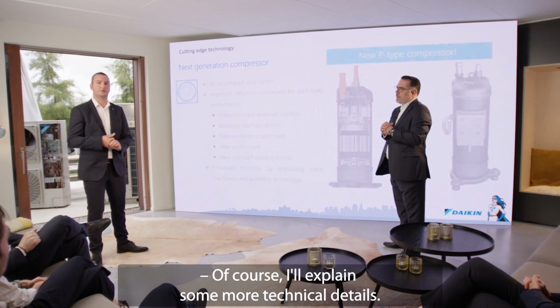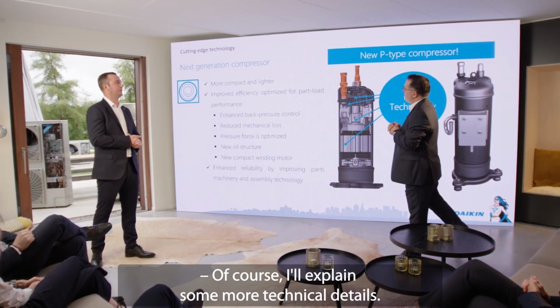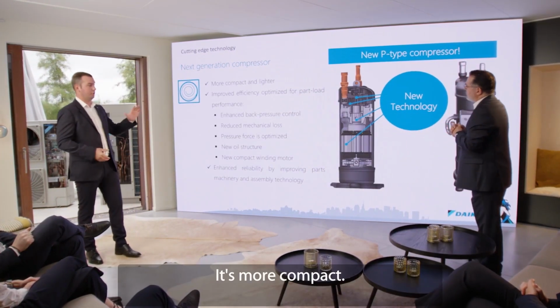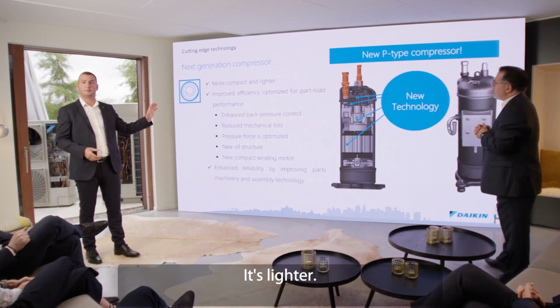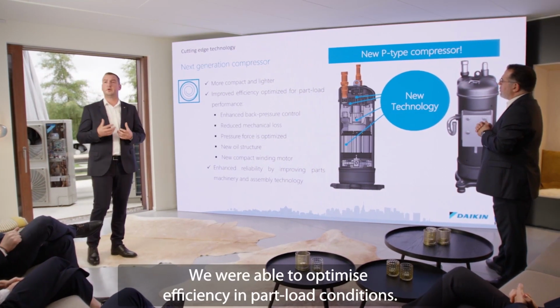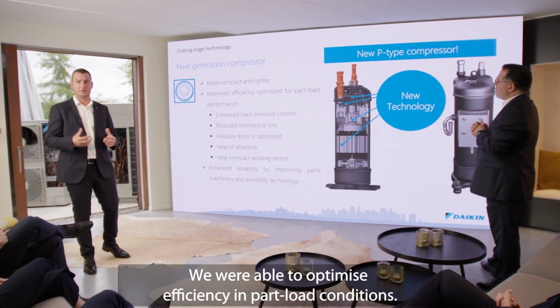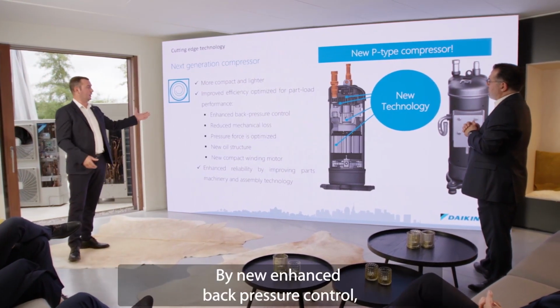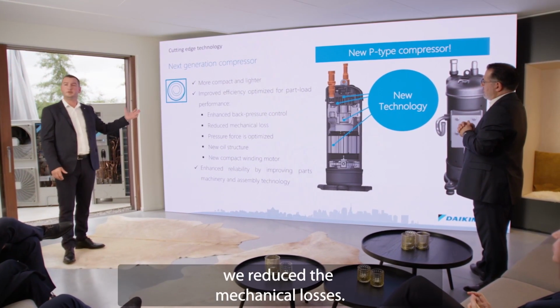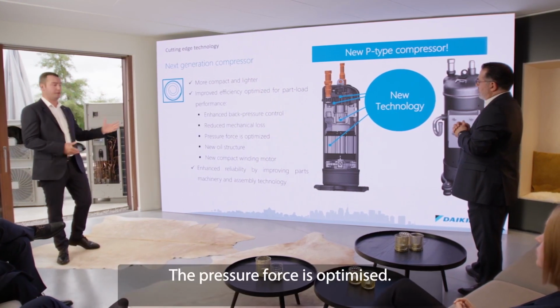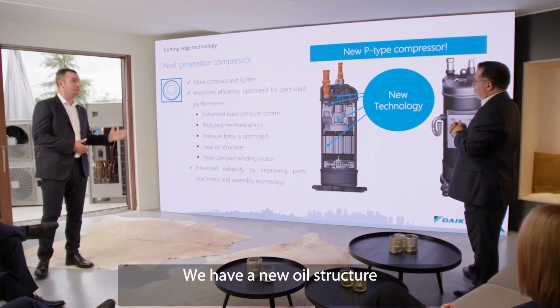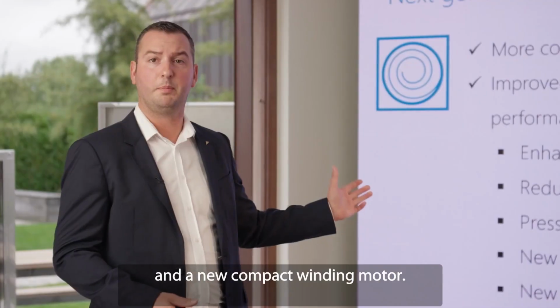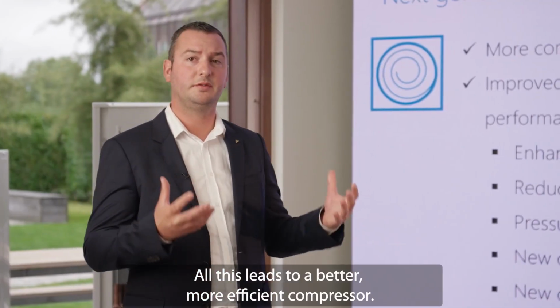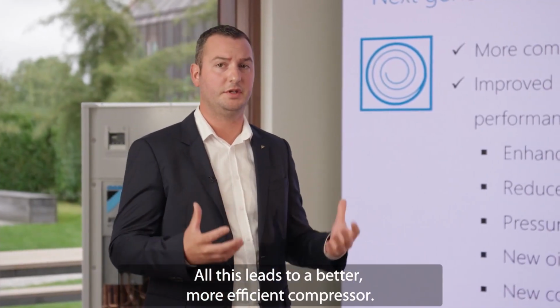Of course, I'd like to explain some more technical details about this new compressor. It's more compact and lighter. Next to this, we were able to optimize the efficiency at part load conditions. With a new enhanced back pressure control, we reduced the mechanical losses. The pressure force is optimized. We have a new oil structure and a new compact winding motor. All this together leads to a better, more efficient compressor.